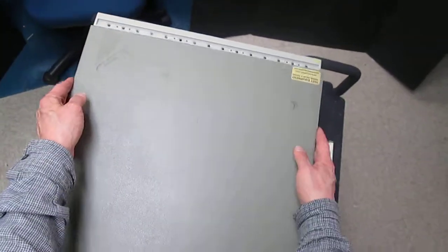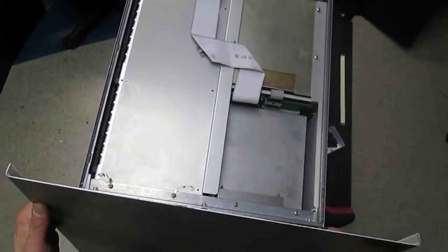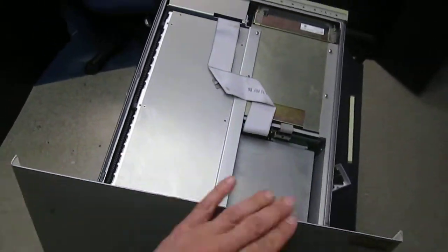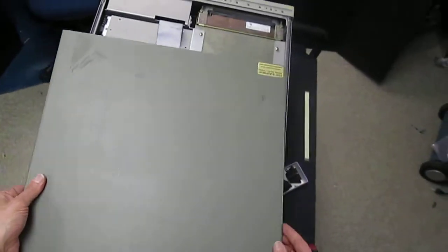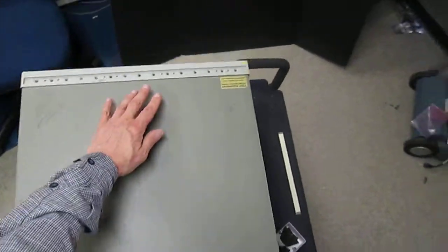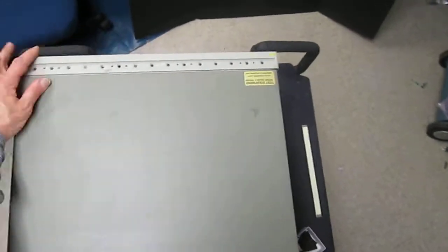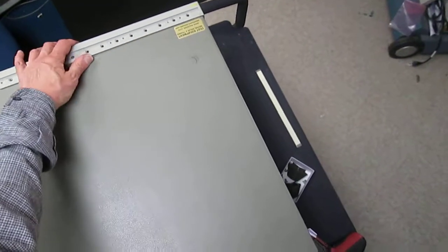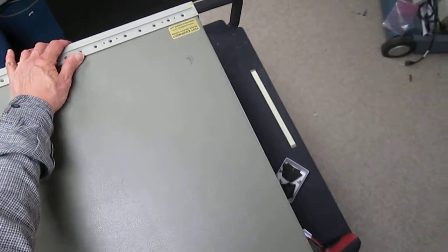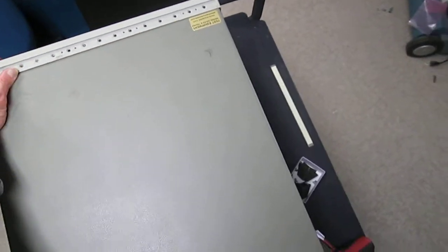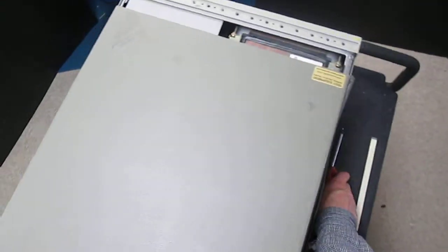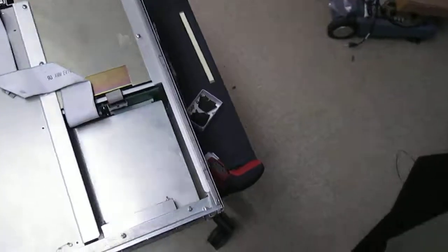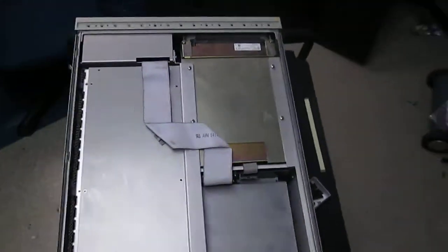Once the front of the top cover clears the bezel, you can just lift it up. Now, when you reinstall the top cover, make sure the edge of the top cover goes into the groove at the back of the bezel. It's very important, because if you start tightening the screw when the edge is not aligned with the gap, you can strip the screw and there will be a lot of trouble. Pay attention to the edge of the top cover when you reinstall it after replacing the display.